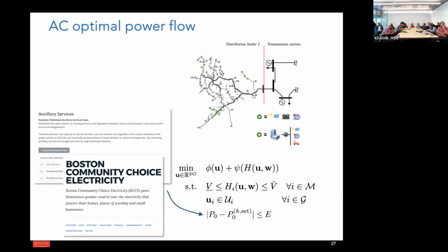Just a side comment, I think it's much easier to measure power accurately than voltage. Yes, and then we can... That's why I'm so sensitive to the accuracy of measurements. Sure, that's true. But then we can solve the power flow equations and find the voltage. The accuracy of voltage measurements in power systems, you will be shocked, is 2%. Really? Yes, it's horrible.